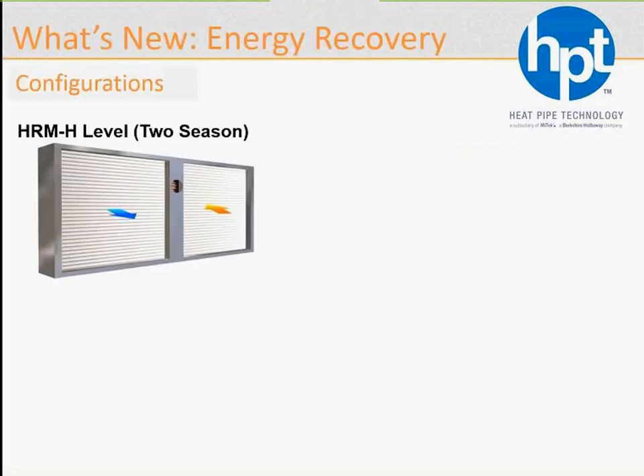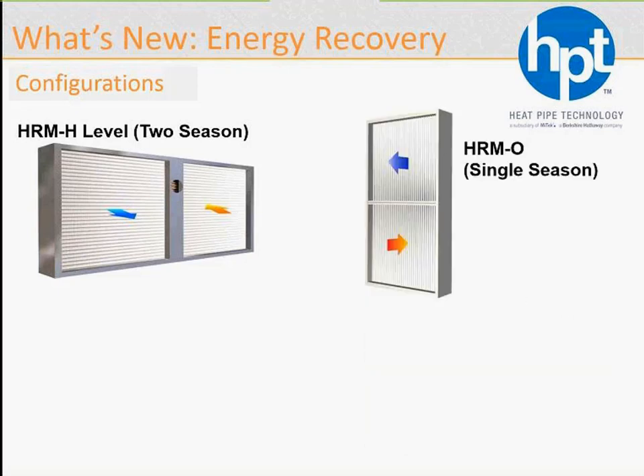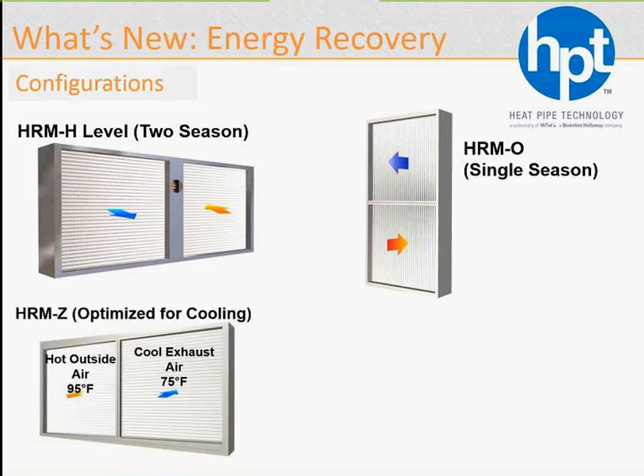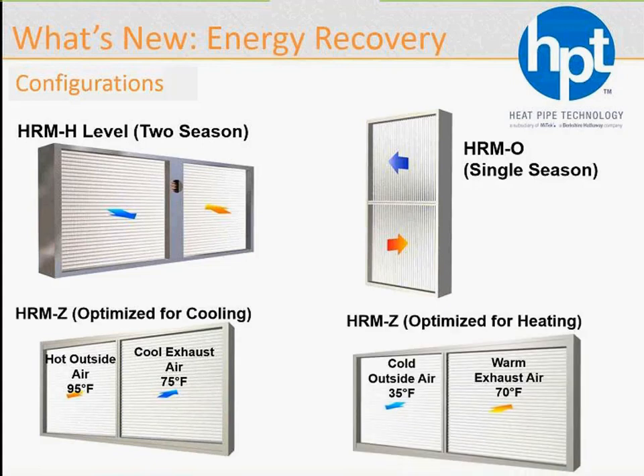First one is what we call HRMH, as in horizontal. You're looking at 2-season recovery. Some geographies have enough or similar hours and BTUs as summer and winter. So this product is the way to go. In the center, you see that gap, and we'll talk about what developments are taking place through that gap. HRMO, the over-under, we mentioned earlier. The optimized for cooling, and then the optimized for heating.